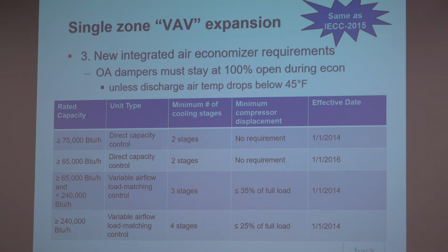However, this requirement did, in some versions of the standard, get put underneath the economizer section because it really was driven by that. It's since been moved out of that section in some of the standards, so it's a little bit independent of that requirement. So you might not have to have an economizer, but you might still need to have multiple stages of compression. It's hard to say. I probably could look that up. Any other questions on this before I move on? Okay.